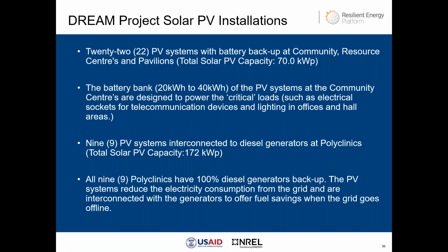Now let's look at the DREAM project's photovoltaic installations. The first phase focused on community centers and pavilions, with a total of 22 systems installed with a combined capacity of 70 kilowatts. These are hybrid systems with battery backup, with battery banks sized between 20 and 40 kilowatt hours. At the community centers, we designated different critical loads to the batteries, such as electrical sockets to power telecommunication devices, and lighting for offices, hall areas, and bathroom facilities, so they would have emergency power during an outage.